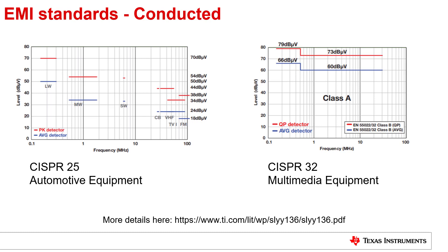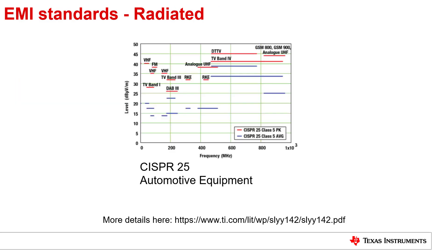The standards are broken into conducted and radiated limits depending on the mode of interference. The bars in the plots here represent the maximum conducted emission limits that can be tolerated while measured through standard EMI measuring equipment for the device under test. Similar standards also exist for radiated interference limits as shown for automotive equipment in this chart. More details about the exact standard and the test methodology can be found in the link shown.